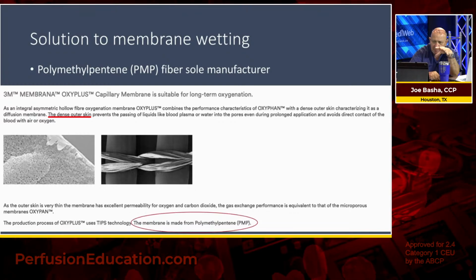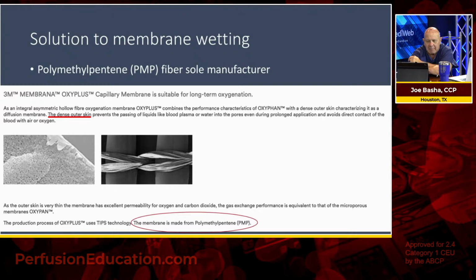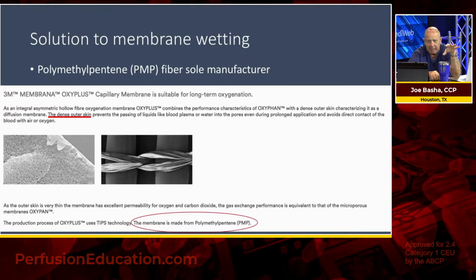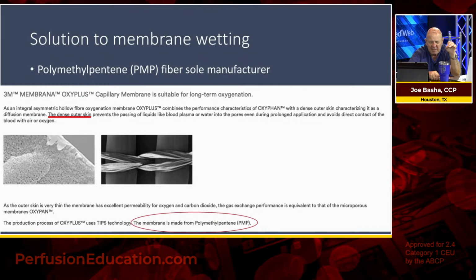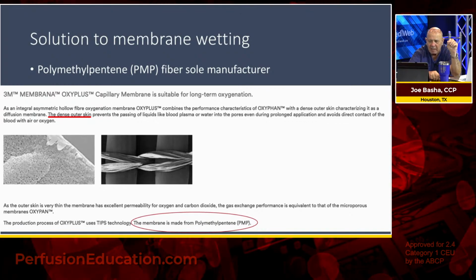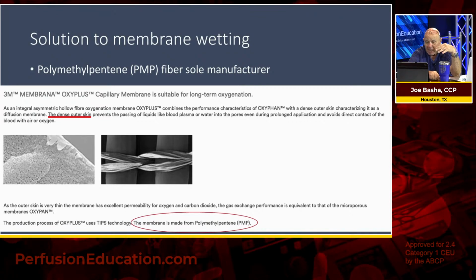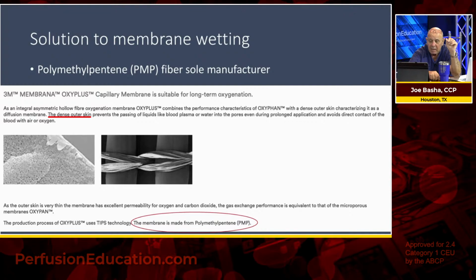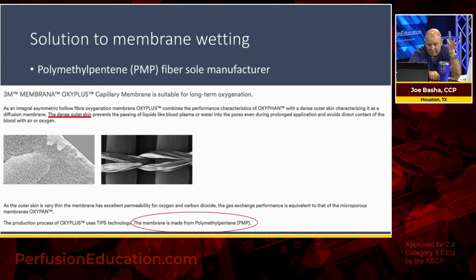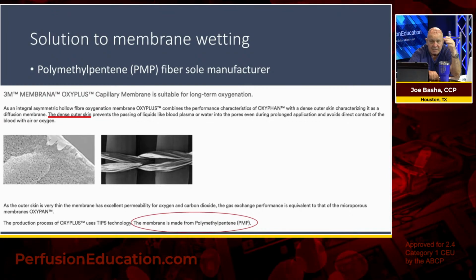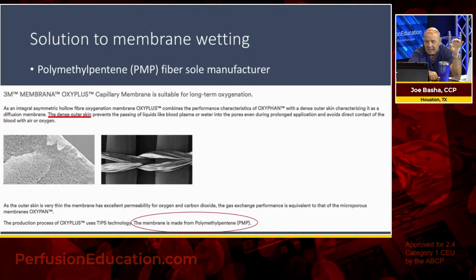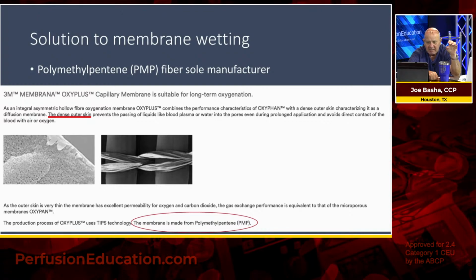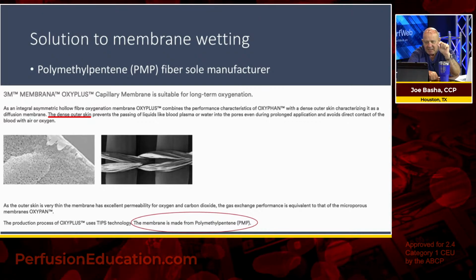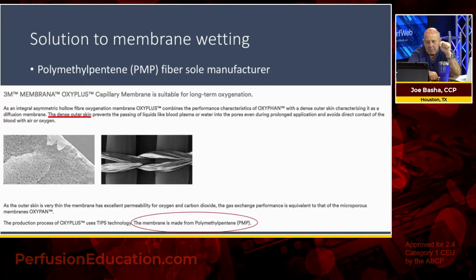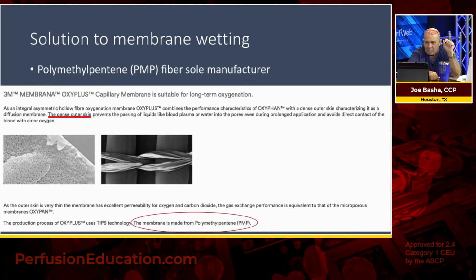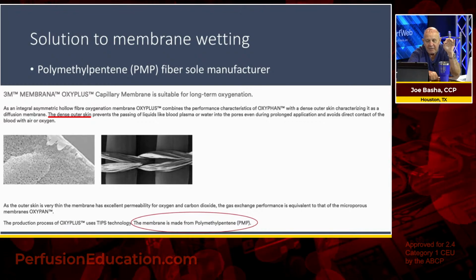So this membrane, as an integral asymmetric hollow fiber oxygenation membrane, again, I consider this submicroporous. They will use the term that this is plasma tight. That's another term you're going to hear a lot of, but they do call it a membrane. I view this as submicroporous versus actual membrane material. And they have an OXYPLUS, which combines the performance characteristics of the OXYPHAN, which is polypropylene, with a dense outer skin characterizing it as a diffusion membrane. This dense outer skin prevents the passing of liquids like blood plasma or water into the pores, even during prolonged application, and avoids direct contact of the blood with air or oxygen.